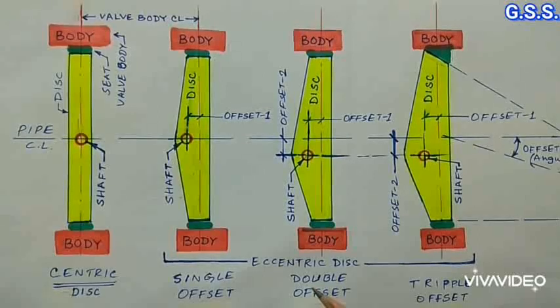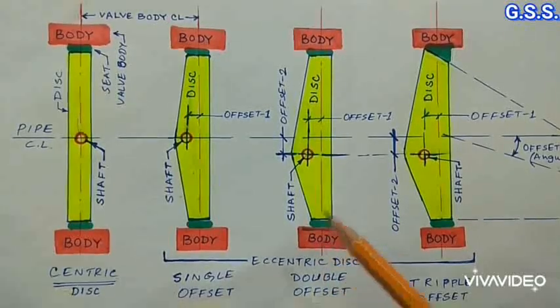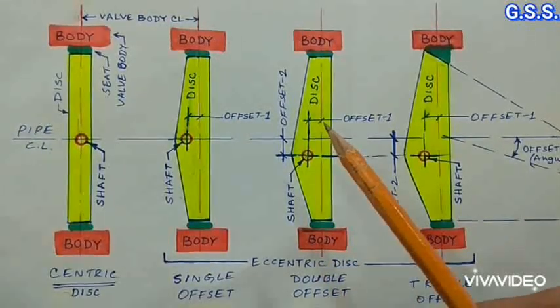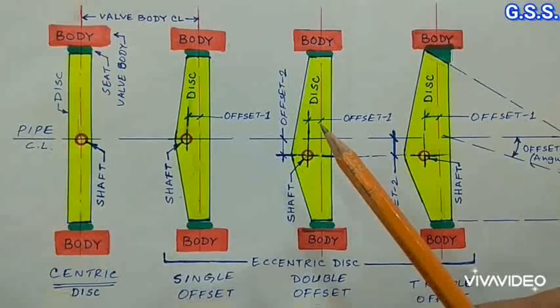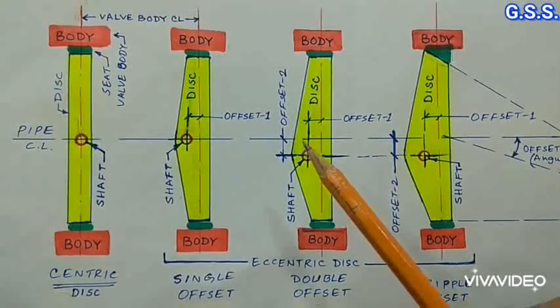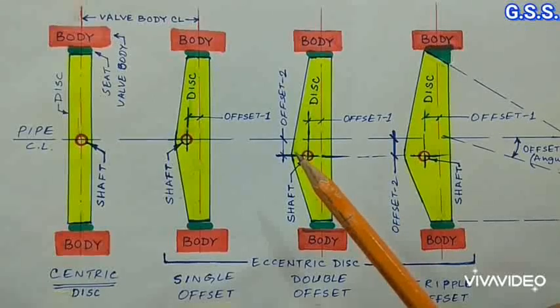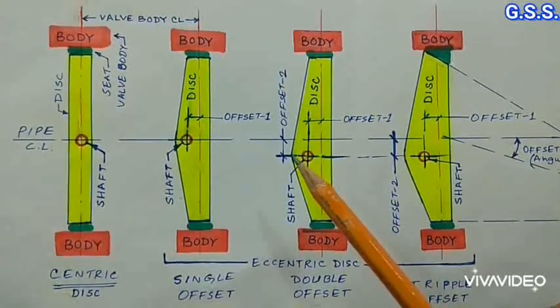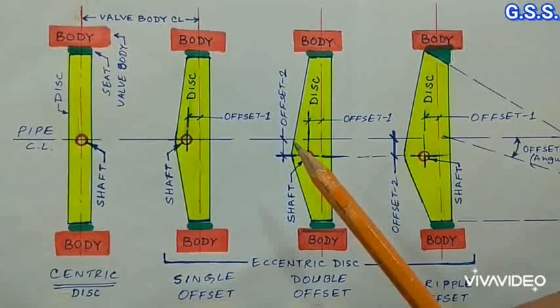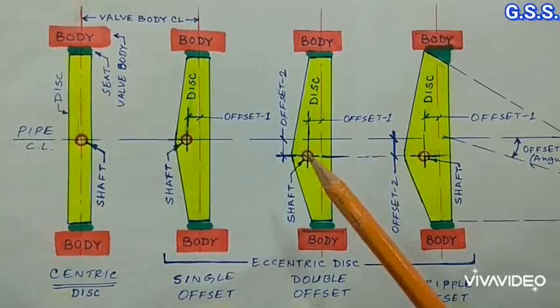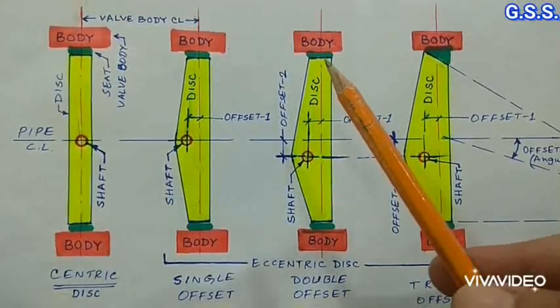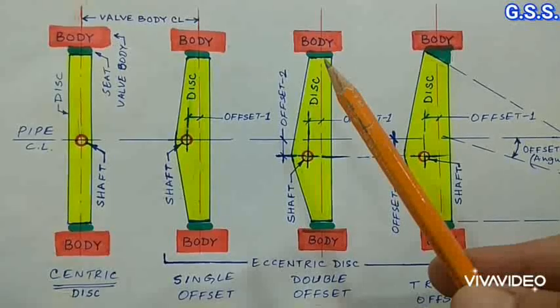In double offset eccentric butterfly valve, first offset is the same as like single offset type. But additionally, second offset is the offset between shaft axis and pipe axis. Due to these two offsets, disc does not touch the seat when opens fully.